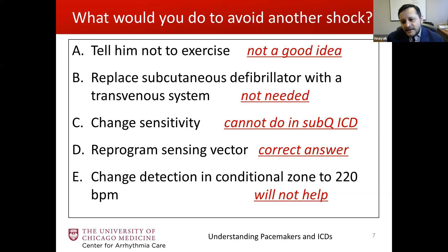And so remember the subcutaneous defibrillator. Here's the generator. Here's the subcutaneous coil. Here's primary, secondary, and alternate. And remember, he was programmed primary. And remember, the device automatically picks the sensing vector based on signal quality, amplitude, stability. But as the implanter, as the following physician, you are able to change that sensing vector.